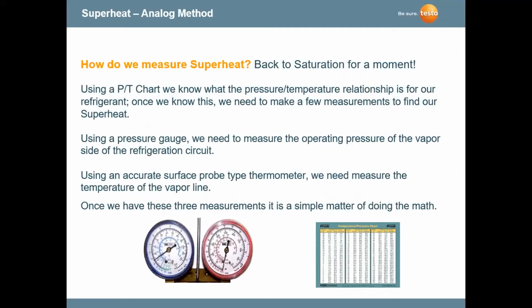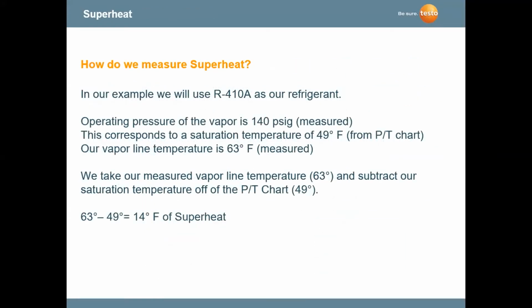The analog method that we've been using since the beginning of time, again, this technology goes back to the early 1900s. The analog gauges that we use to get the pressures. We're using a temperature measurement, hopefully an accurate surface probe thermometer, and we're doing the math by converting the pressure to the saturation temperatures using a PT chart.